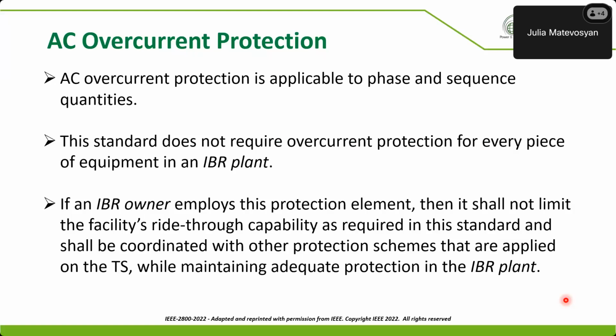Next one, AC overcurrent protection. So again, this is applicable if the protection is detecting overcurrent on a phase A, B, or C basis, or detecting overcurrent on, say, positive sequence or negative sequence quantities. Again, the standard does not say that something in the plant has to be protected by overcurrent protection. But the standard says if overcurrent protection is used within the plant, either at the plant level or individually in the inverters or wind turbine generators, then that protection shall be set such that it does not limit the facility from meeting its ride-through obligations based on the standard.